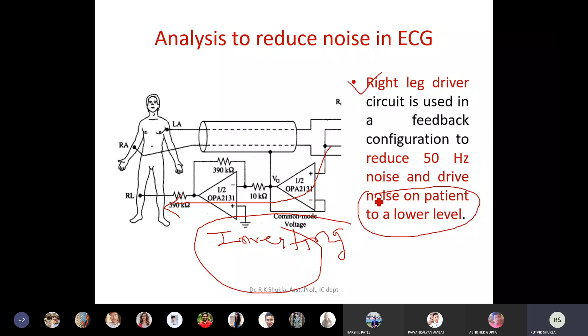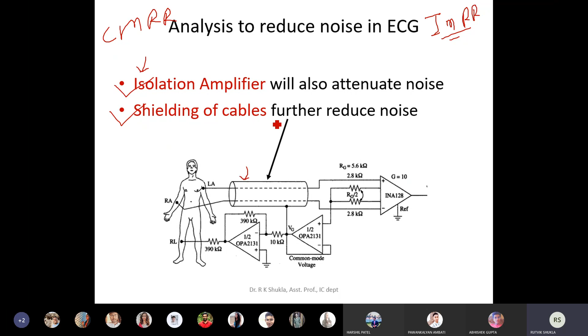The third defense is that we are using an isolation amplifier, which will also attenuate the noise. This will also come in the second part, when you learn about the isolation amplifier. Just as the instrumentation amplifier has CMRR, the isolation amplifier has IMRR, the isolation mode rejection ratio. So the isolation amplifier also has the capability to attenuate the noise. And the last defense which we are using is shielding of cables. The cable is shielded by a particular material which reduces the noise further.